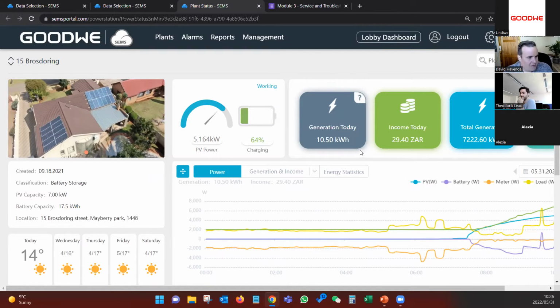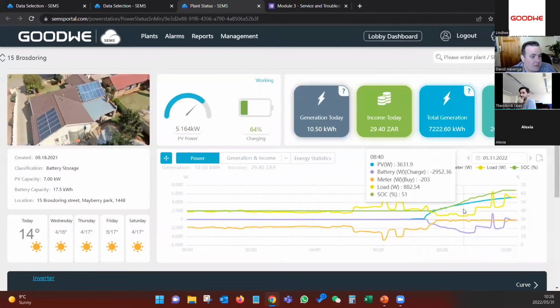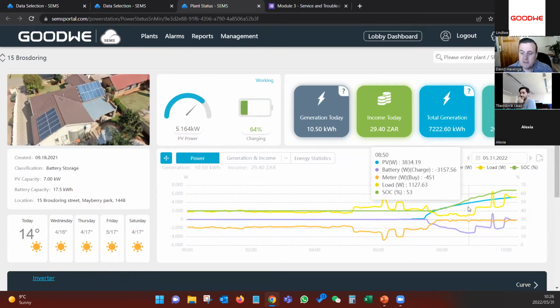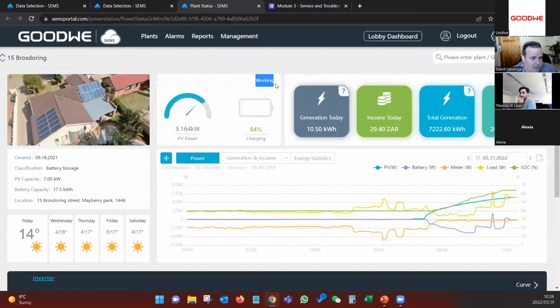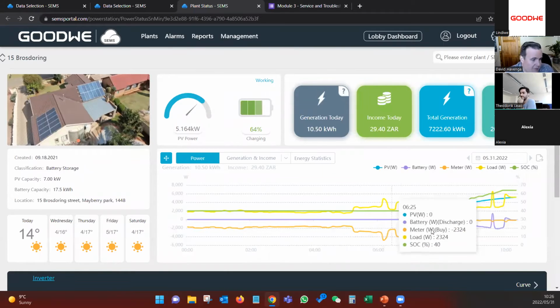Then next we have the plants. So when we are diagnosing any faults, our plant itself can also give us a lot of information. Normally, it can give us a status, whether it's working, fault, or anything like that. We have our battery SOC here. As you'll see, the SOC is here as well. But when we have multiple batteries or multiple inverters with batteries on a plant, it won't display the battery SOC in this graph, but we can see the overall battery SOC here, as well as open another graph to view the battery SOC graph.